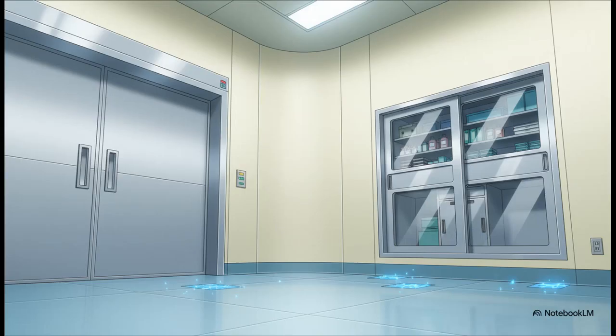So the room itself is literally fighting contamination and hazards. The edges and corners where the floor meets the wall are actually rounded off, meaning no sharp 90-degree angles where dust can easily accumulate. Cabinets are recessed directly into the walls with sliding doors to save space and maintain asepsis. The door frames are huge, a minimum of 5 feet wide, so you can safely maneuver beds and equipment. But the craziest feature? The floors themselves are impregnated with conductive material. This creates a pathway for electricity to be conducted away from personnel and equipment, preventing the dangerous buildup of electrostatic charges.